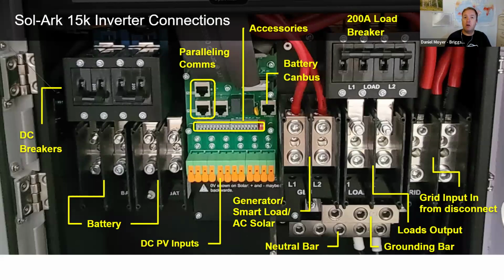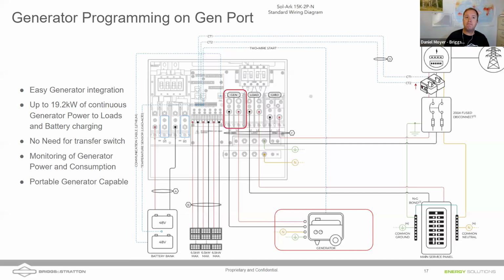In the center is our loads output. That's rated 200 amps. On the far right-hand side is our grid input. The 200 amp, we've got a typo there, Nathan. That's technically not a breaker. That's just a load disconnect. So you are still going to want to see a breaker on the load panel where you're going to have your home distribution as well. Load out, that is correct. I mean, you will have your overcurrent protection built into the Sol-Ark software, but to meet code requirements on wiring, you need to have that breaker there. Yep, thank you. The grounding bar and the neutral bar are down there at the bottom as well. And I like that they have a lot of space down there at the bottom and make some of these connections pretty easy.